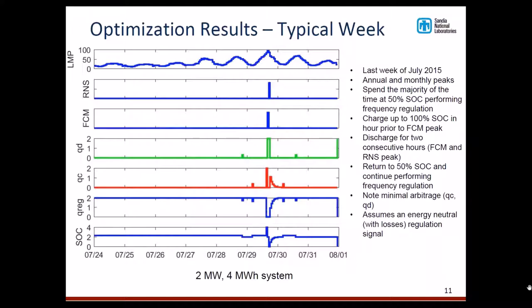Since frequency regulation provides the most revenue, the optimal policy is just to hang out at 50% state of charge most of the time, and then do frequency regulation all the time. But this particular week has a peak hour in it, so if you knew that in advance, you would charge up to 100% state of charge, which is what happens. Then you just discharge during the peak hour and capture that benefit as well, and then go back to doing frequency regulation.